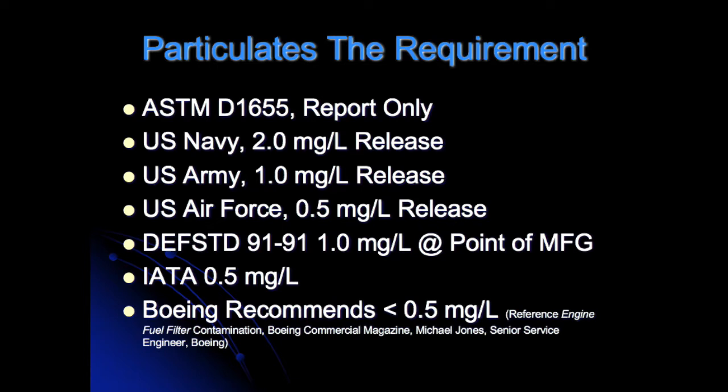The particulates requirement for fuel contamination is as follows. ASTM D1655: report only. The U.S. Navy has a 2.0 mg per liter release. The U.S. Army has a 1.0 mg per liter release. The U.S. Air Force has a 0.5 mg per liter release. Def Standard 9191 has a 1.0 mg per liter at point of manufacturing. IATA has a 0.5 mg per liter and Boeing recommends less than 0.5 mg per liter.